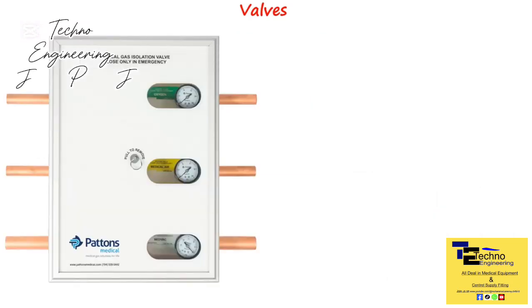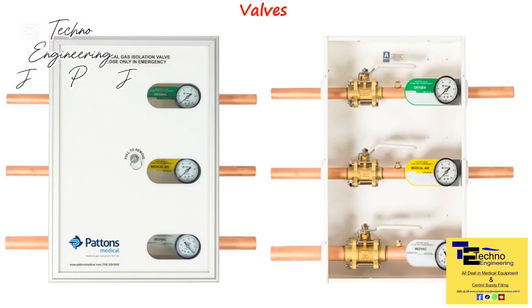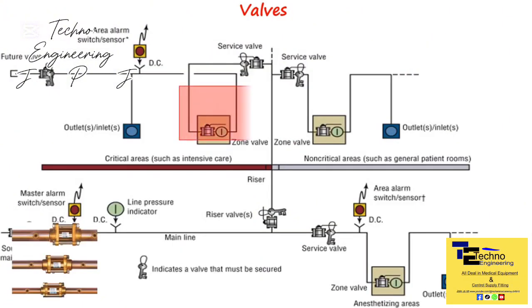Shut-off valves, divided into manual and service types, enable isolation of the piping system for troubleshooting and maintenance without whole system shutdown. Manual or zone shut-off valves must be installed in locations that are visible and accessible at all times. These valves are typically housed in boxes with breakable or removable windows. Each valve should be clearly marked to indicate its function, the type of gas it controls, the specific area it oversees, and a cautionary note emphasizing that it should only be closed in emergency situations.